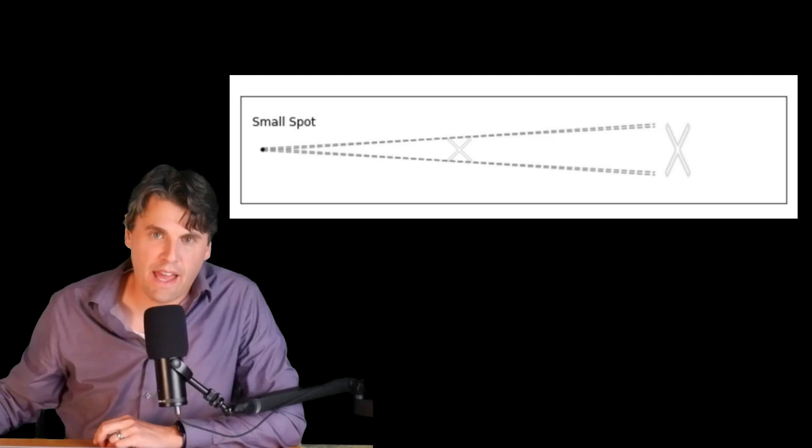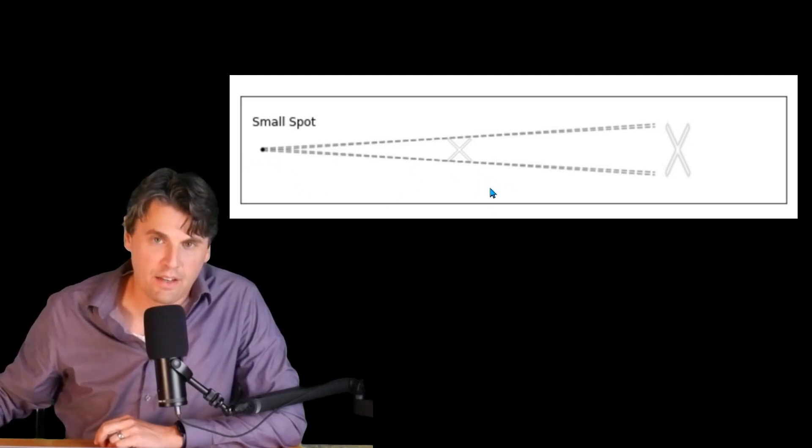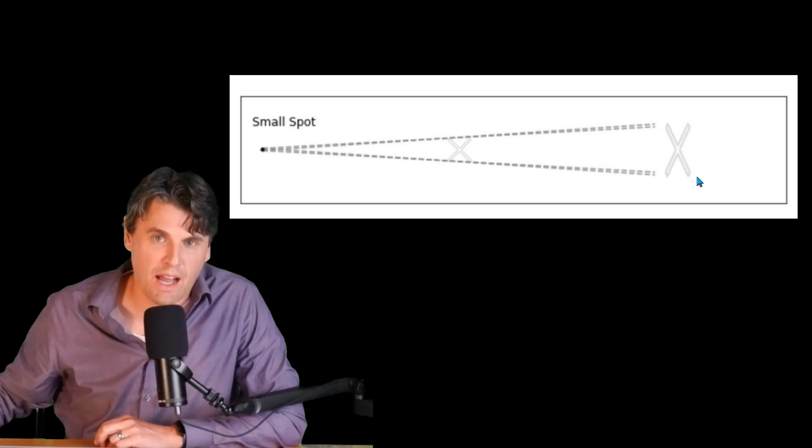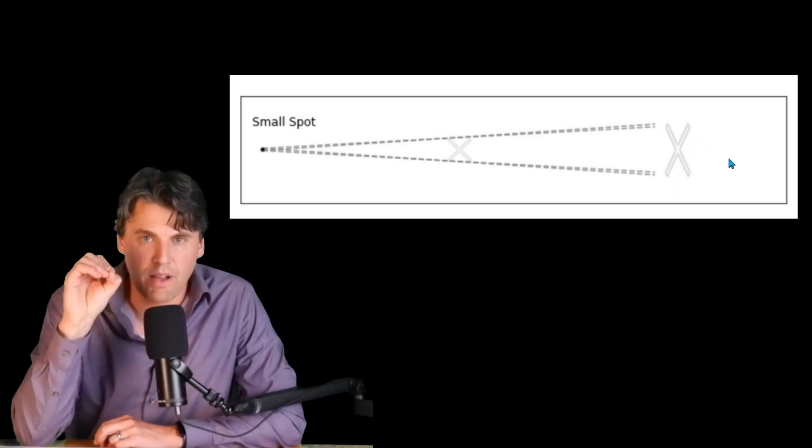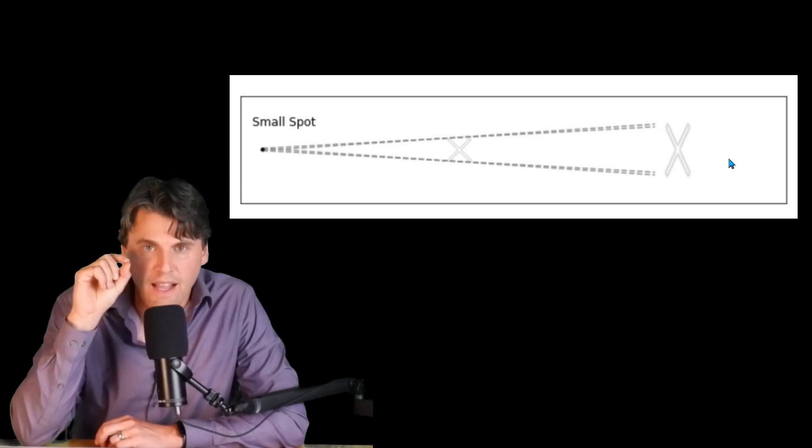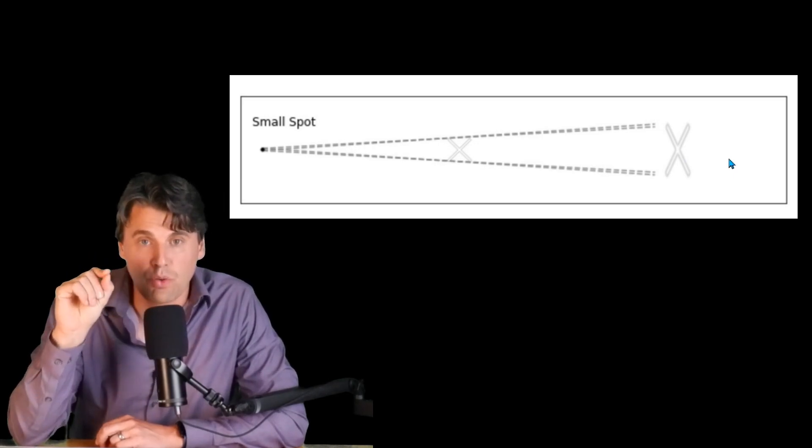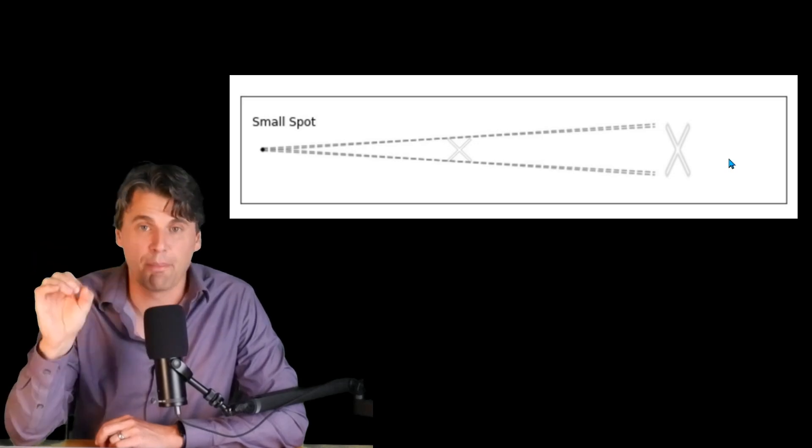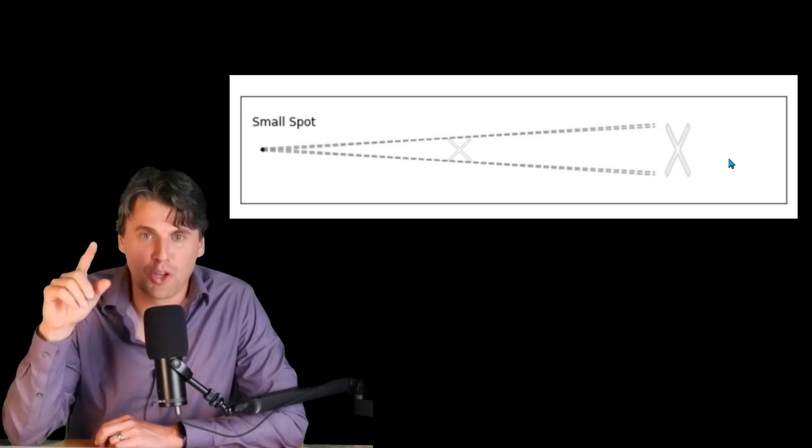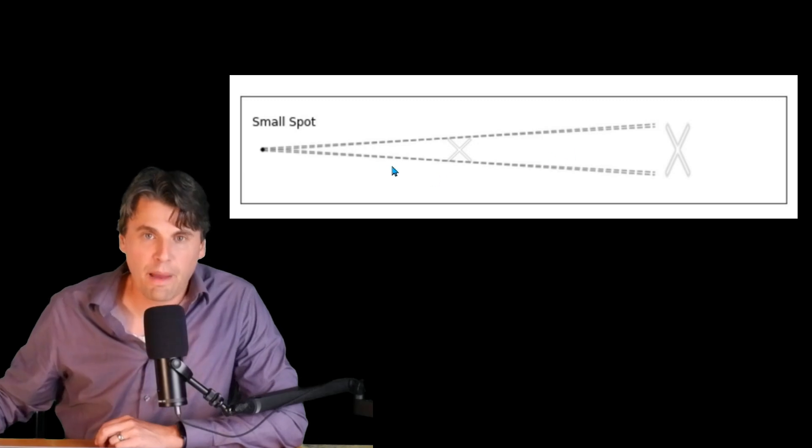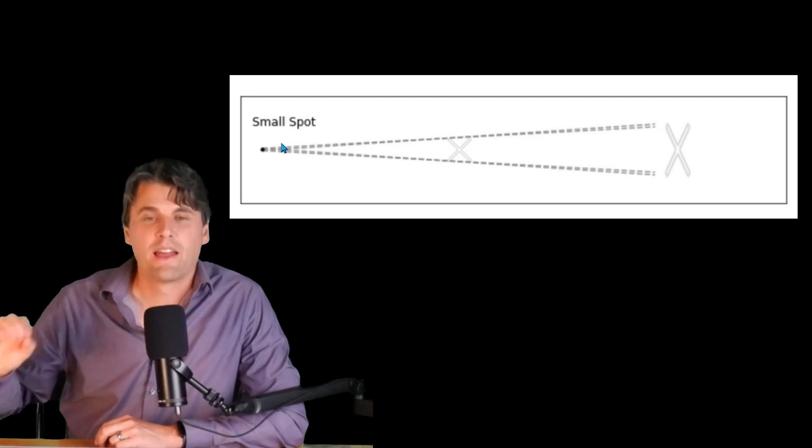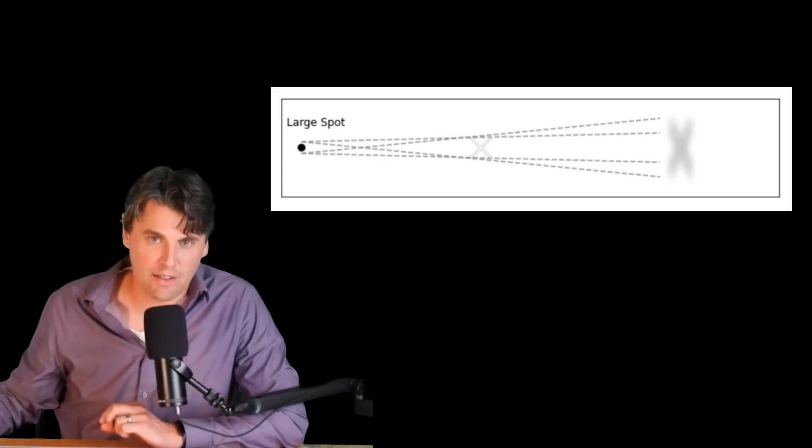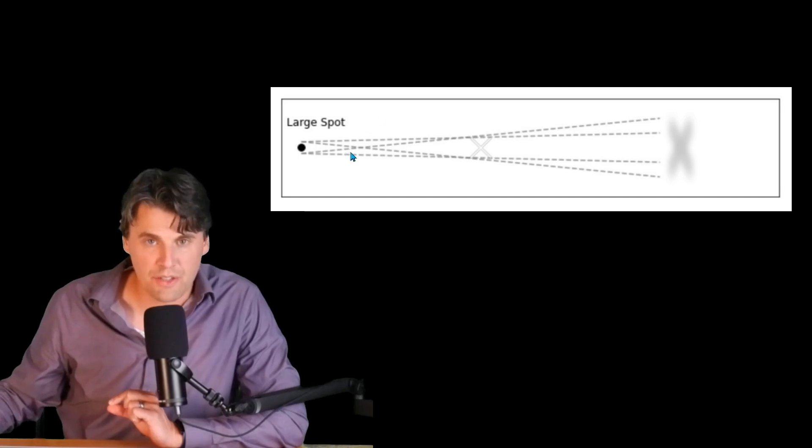We have a focal spot right here. The letter X is going to be standing up right here. And then our image that's going to be on the image receptor is going to be down here. And what we're showing first is actually the contribution due to the focal spot blurring. We call this geometric unsharpness. U for unsharpness is used a lot of times. Imagine you have a point for a focal spot. That's the best scenario. And then if the focal spot gets a little larger, and larger still, there starts to become more blurring at the edges of the actual image.